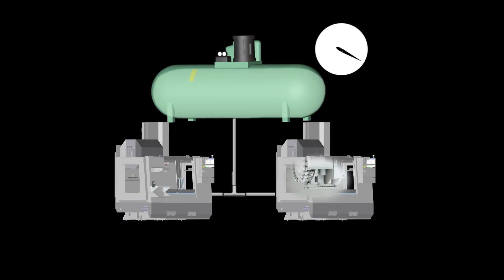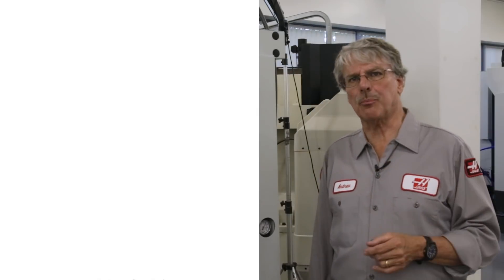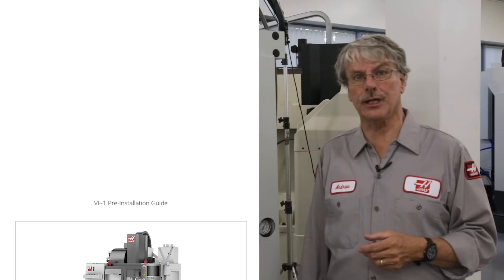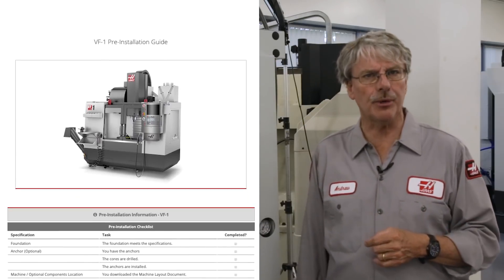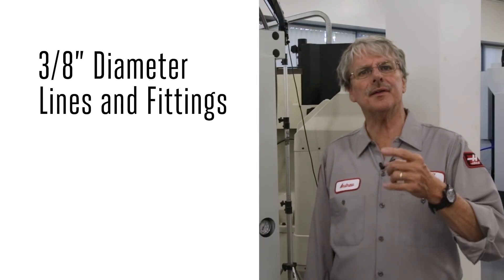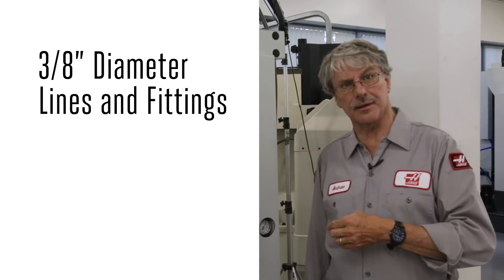We publish a pre-installation guide for each machine that we sell. For the VF1, we recommend 4 standard cubic feet per minute, or SCFM, of air. We also suggest 3/8 inch diameter lines and fittings. Getting the right air volume to the machine is kind of a two-part equation.